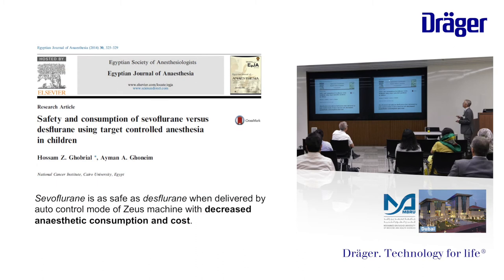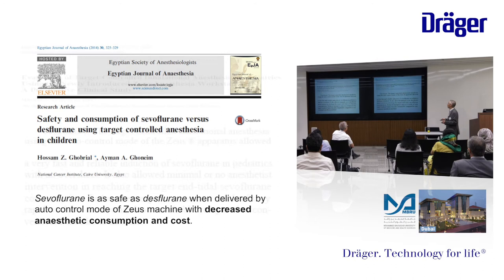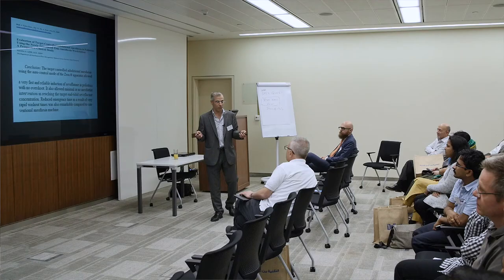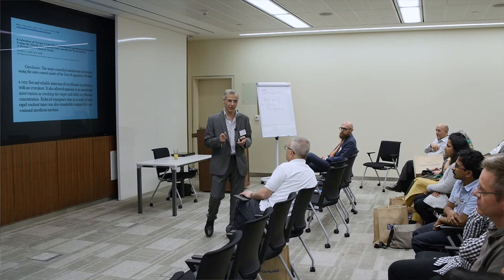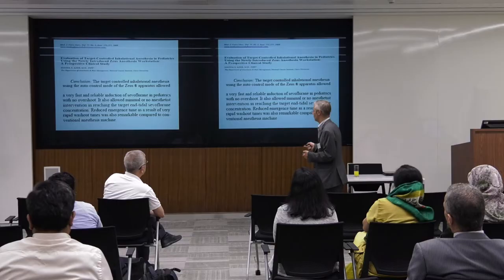Sevoflurane is as safe as desflurane when delivered by the auto control mode of the Zeus machine, with decreased anesthesia consumption and cost. And finally, evaluation of target-controlled inhalational anesthesia in pediatrics using the newly introduced Zeus anesthesia workstation concluded that TCIA using the auto control mode allows very fast and reliable induction of sevoflurane in pediatrics. This was the point of discussion with Dr. Fawaz — can we use it? Yes, we can use it and it will compensate very fast. We couldn't find a scientific reason for his concern from our point of view.